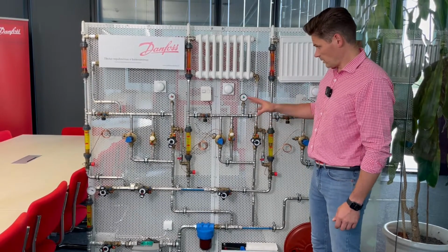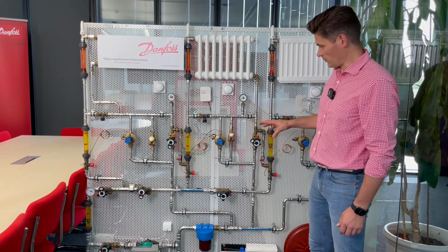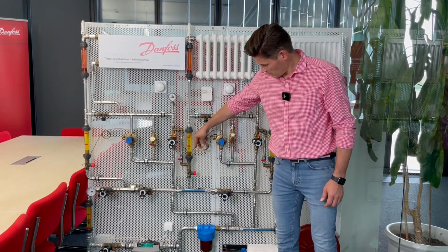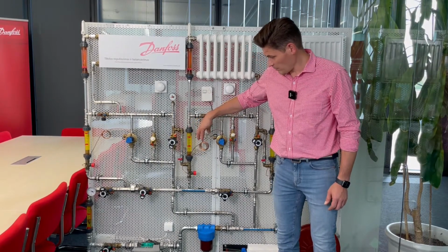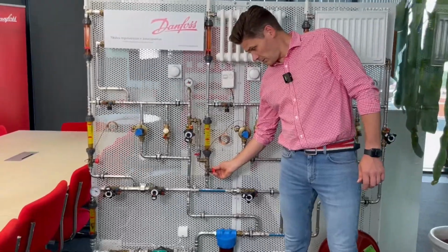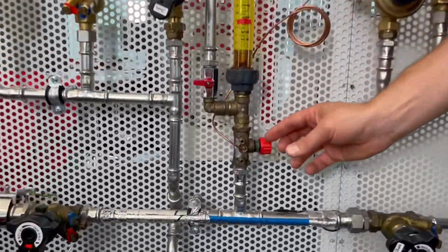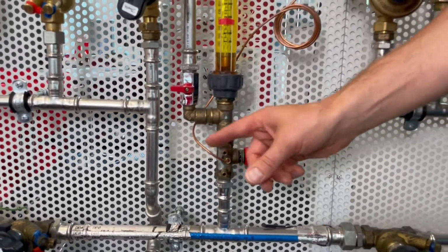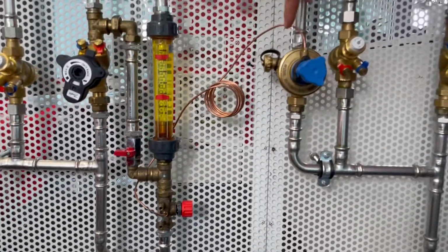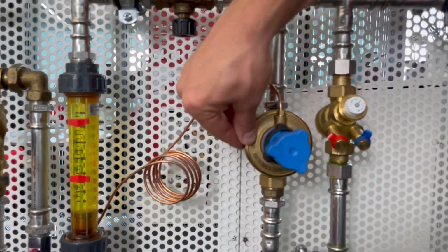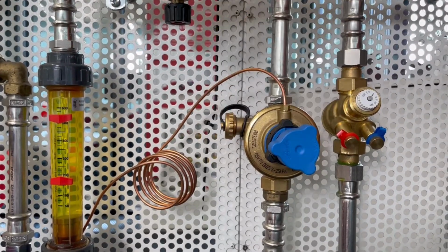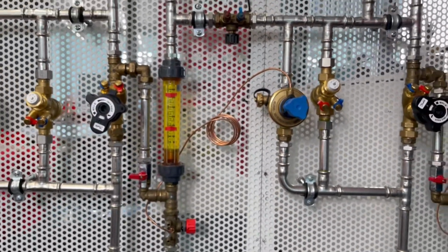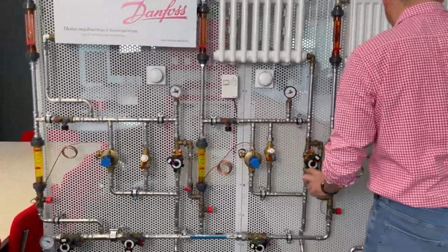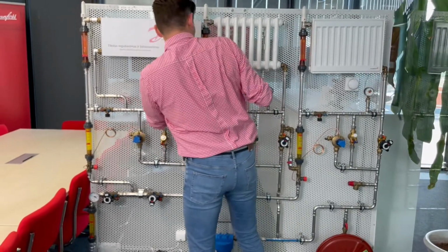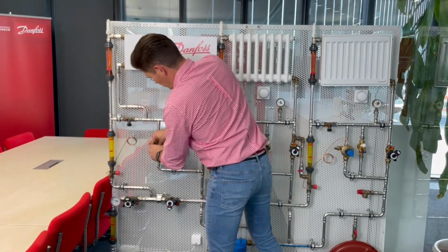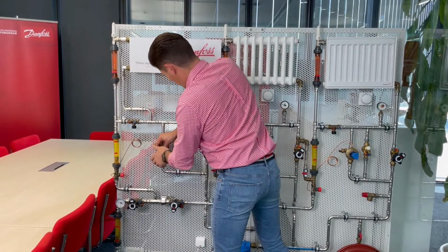And now we will see how it works with two types of automatic valves. The first one will be done for ASV-PV, a delta P controller. We have here a balancing valve, which is more or less used for connection, to have the possibility to connect an impulse tube, and here goes the impulse tube, and the membrane maintains the needed pressure on our riser. So I close these manual balancing valves, close them all. I open up everything in the system. I open up the pressure controllers, the delta P controllers.